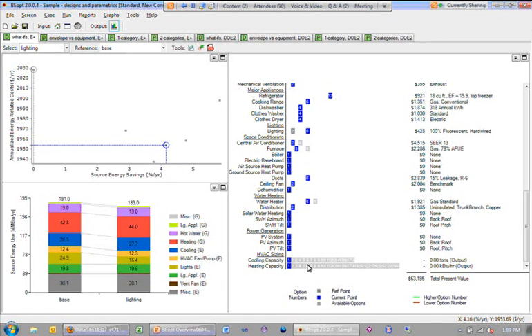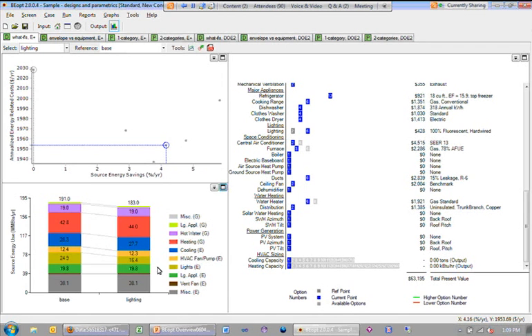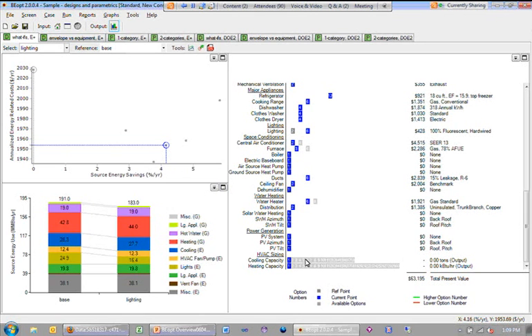Generally speaking, what you would see is you could see a downsizing benefit if you had auto-sized this building that the fact that you put in more efficient lighting, you have less demand on your HVAC system, and therefore, you could have a smaller HVAC system that could be reflected here in terms of an output.